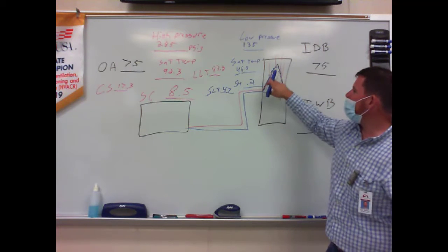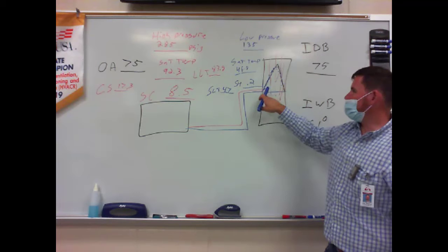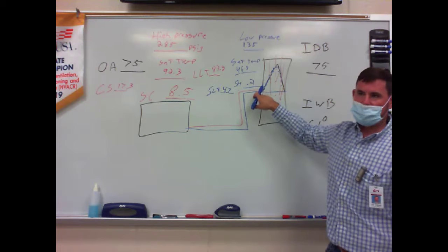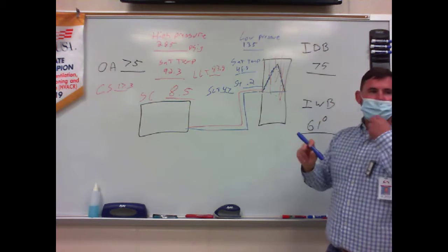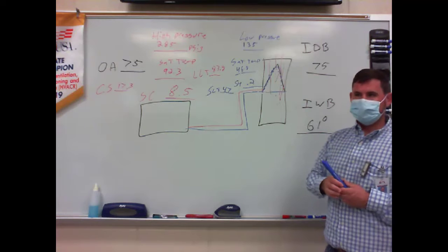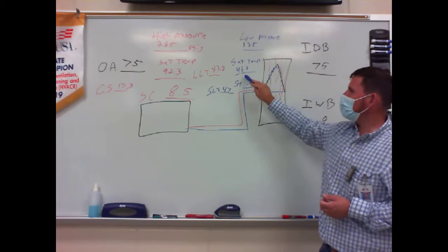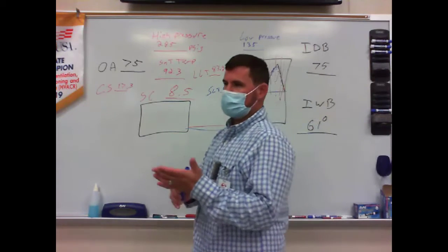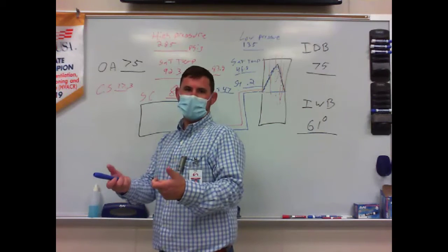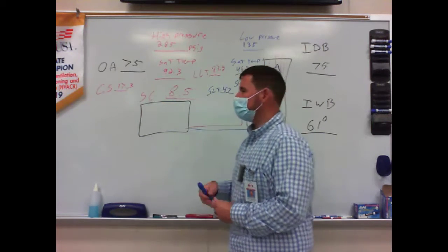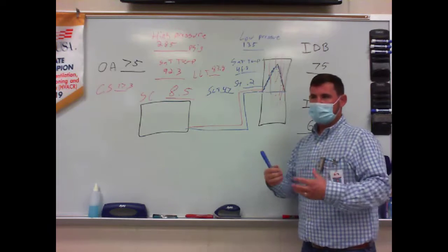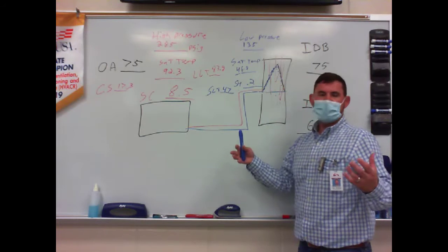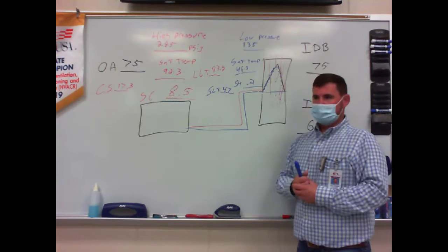I would want to know that all my liquid boiled off into a vapor, and it's coming out as all vapor. If I have 0 degrees superheat, that means that I'm coming out as both liquid and vapor still. Does that make sense? The only way I know that it's all vapor is if I have some superheat. In this case, I don't. 0.2 is not significant because I don't know how accurate my pressure reading was, and I don't know how accurate my temperature reading was. So I can't say that I legitimately have anything above saturation. But if I had 12 degrees above it, then I'd know that I was all vapor coming out. Does that make sense?